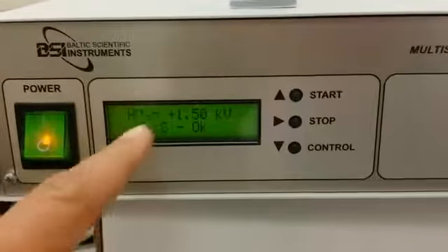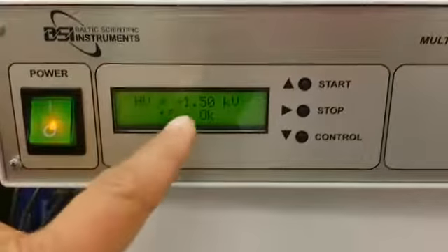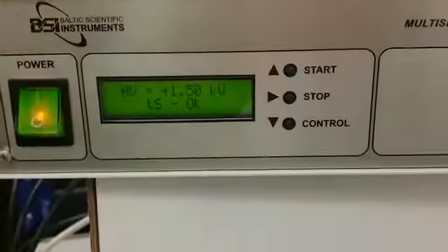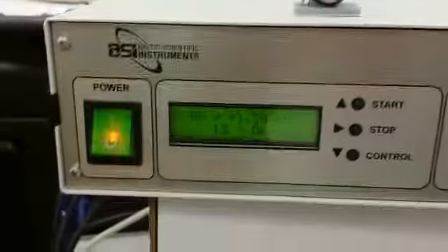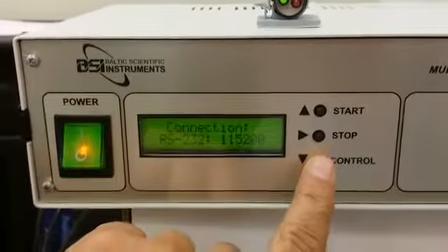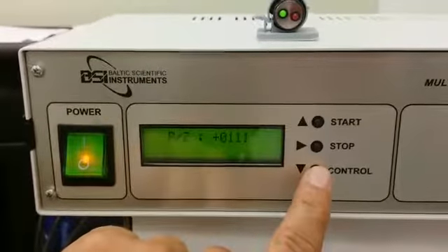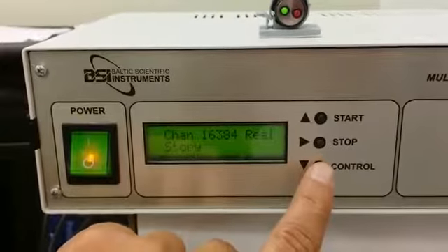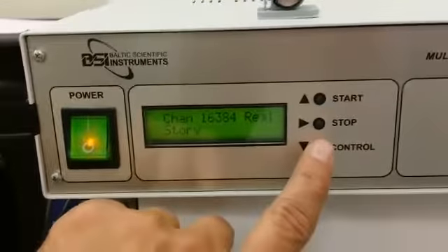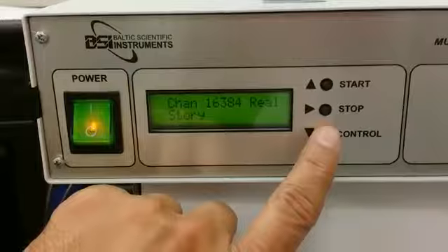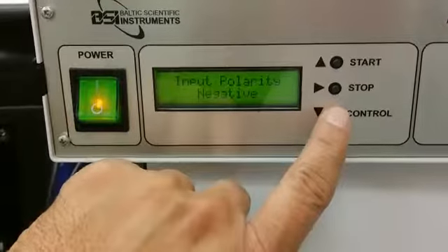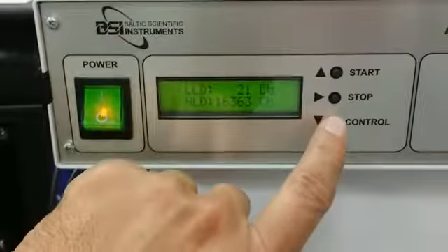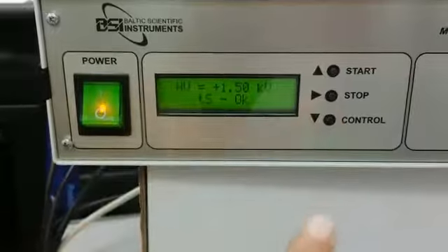In your detector, your high voltage should be set at plus 2.00 kV because your detector is slightly bigger than our detector. And then we set the high voltage, we set the baud rate, we looked at the pole 0, whatever it comes up. And now from this part onwards, I am assuming that your high voltage is already on, as my high voltage is already on. No need to turn on and off the high voltage all the time.